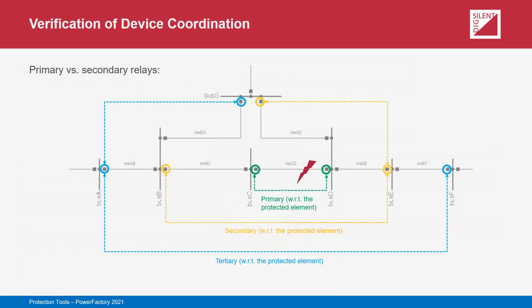For each bar, an expanded report can be generated which details the tripping time of each relevant protection device for each fault location and highlights the role it plays. This report can be used to more accurately diagnose the cause of any tripping or fault clearance time issues. For the verification of device coordination, the results from the topological search are again used. The tool automatically identifies the relays expected to provide primary, secondary, and tertiary protection for the applied fault, and identifies which relays are upstream and downstream in relation to the applied fault and are therefore expected to coordinate with one another.